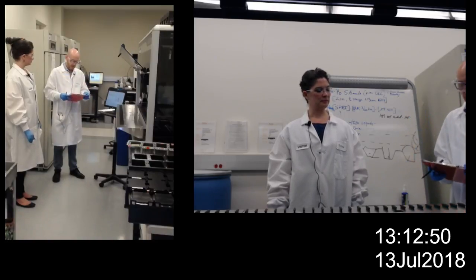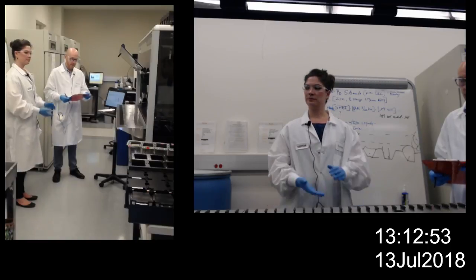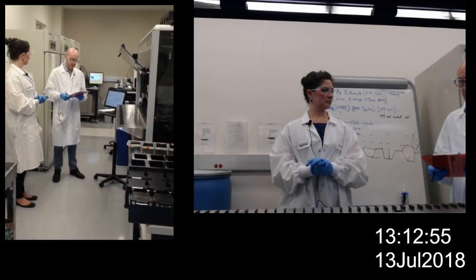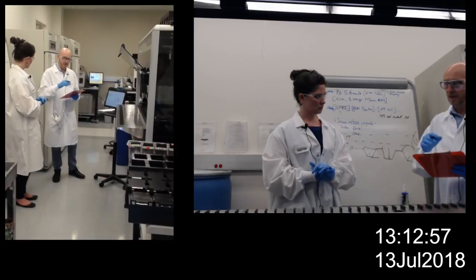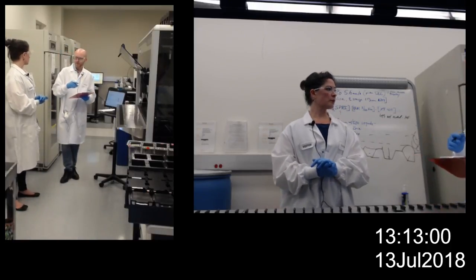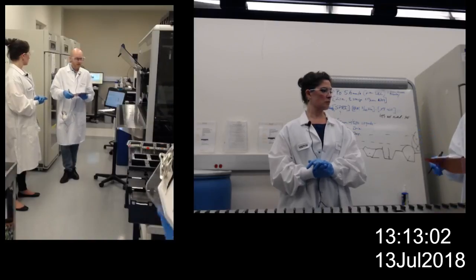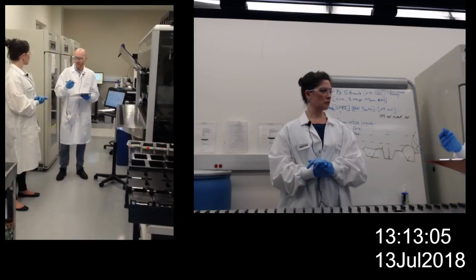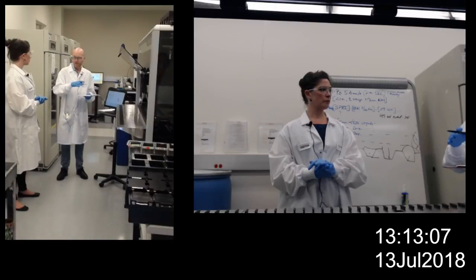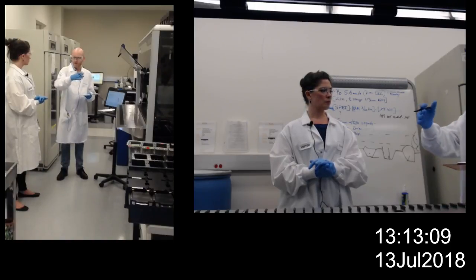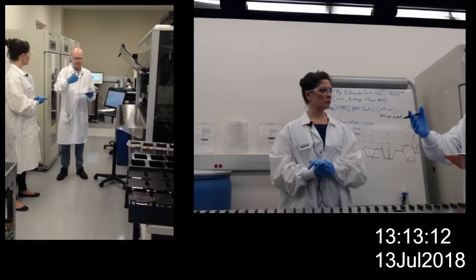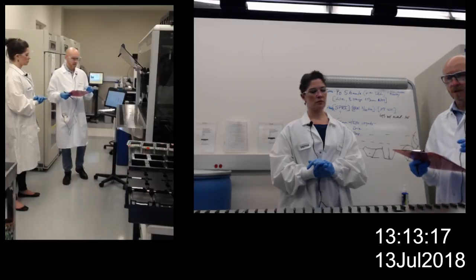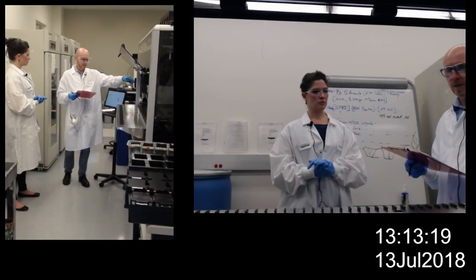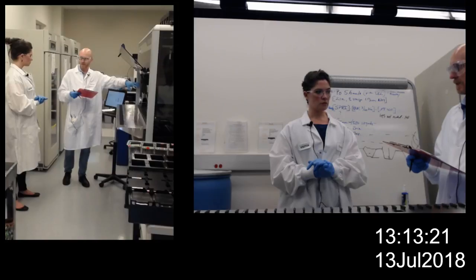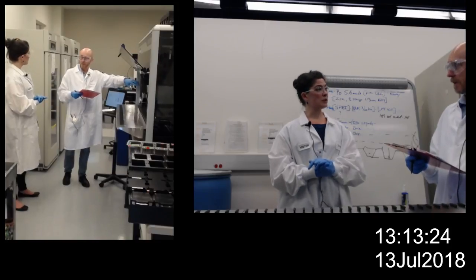So just before we go into the first scenario, I'm going to go over some more information about the system and about the workflows for the system. You may or may not know them already, but there's a 24/48 sample workflow, which is one deck setup, and a couple of interactions during the workflow until they get to qPCR, and then the pools or libraries are pipetted by the robot into the reagent cartridge for the NextSeq DX. It goes right into the cartridge.